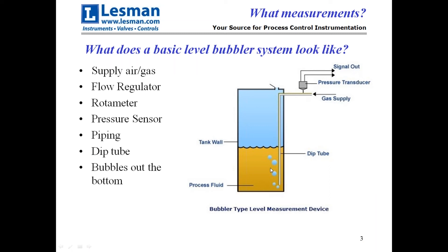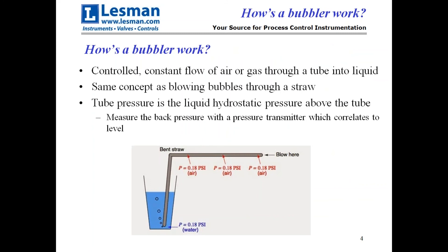Before we get into the details of each application, let's go into what makes a basic bubbler. A basic bubbler has some kind of supply air or gas that comes into it, goes into a flow regulator, flows down the tube, and makes bubbles in the liquid. In order to get a measurement, we've got either a pressure transducer, a gauge, or something up on top that tells us what the back pressure in the tube is. That's your basic bubbler.